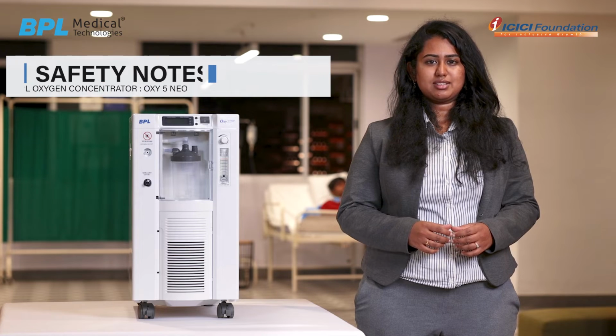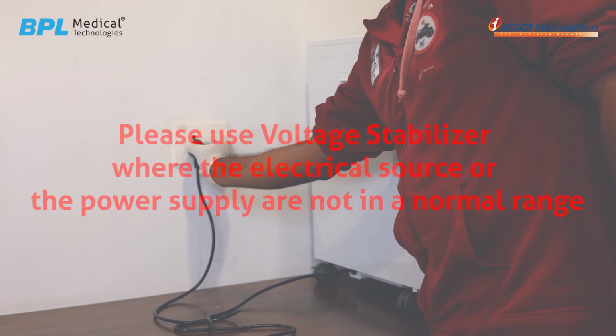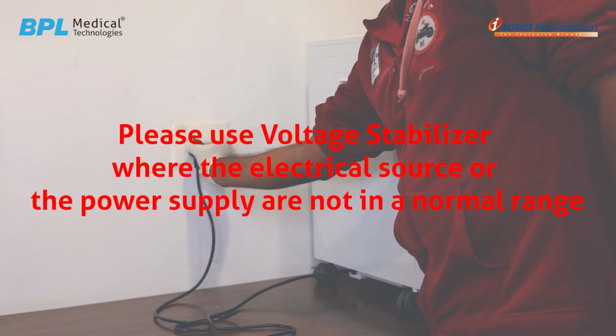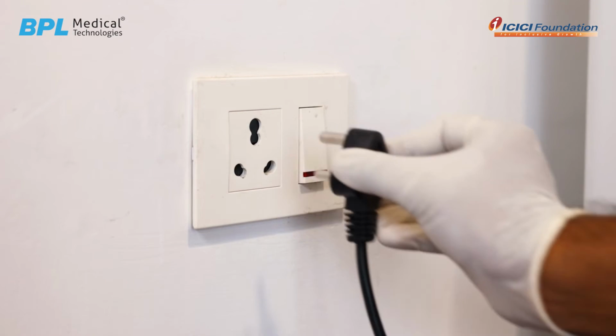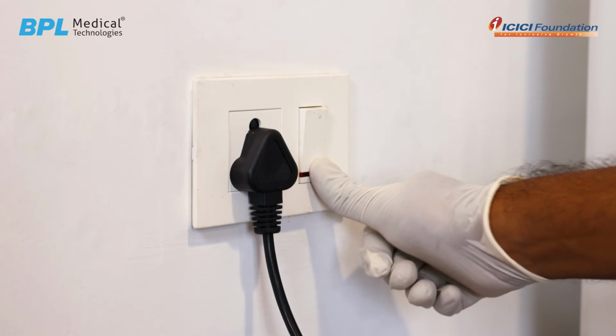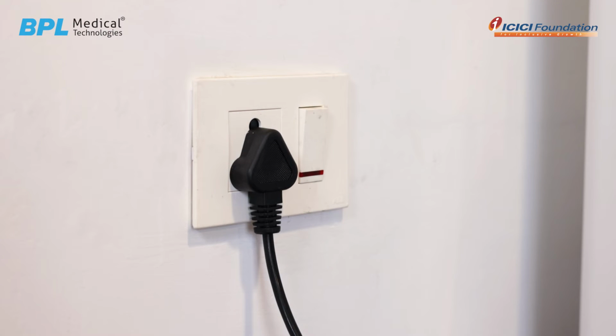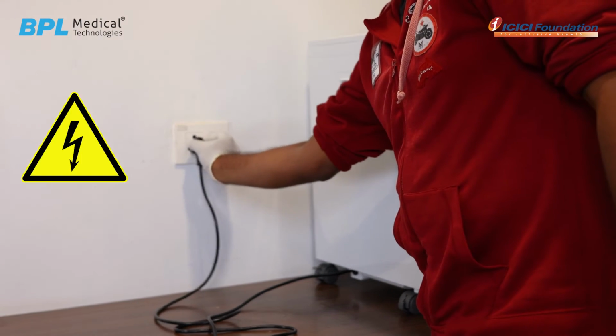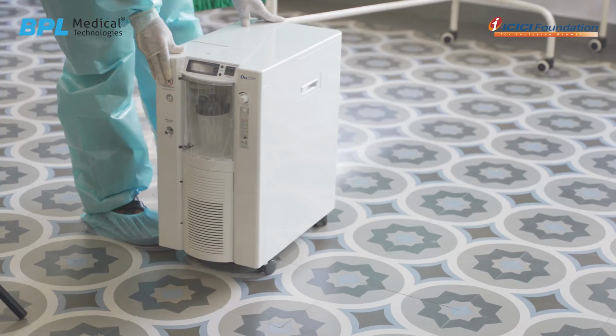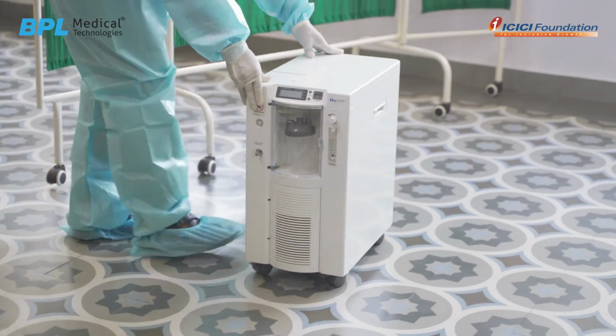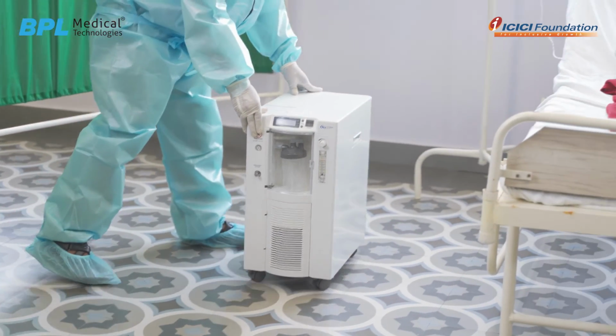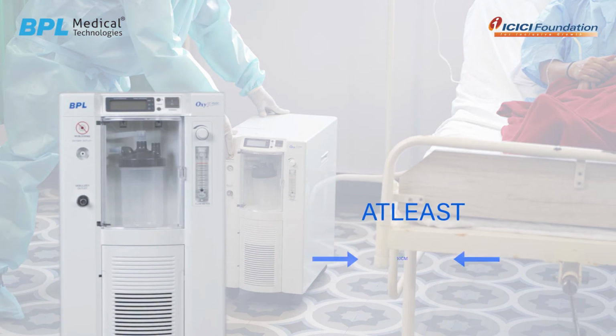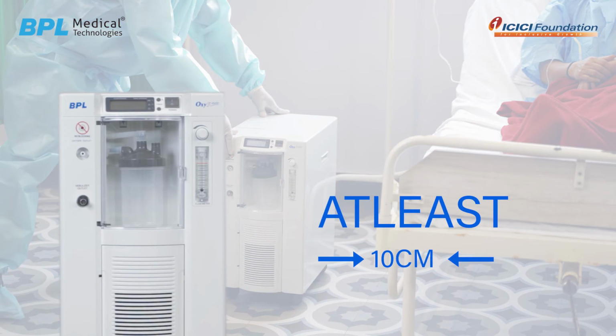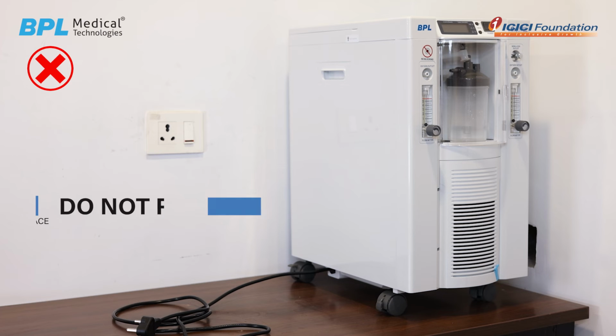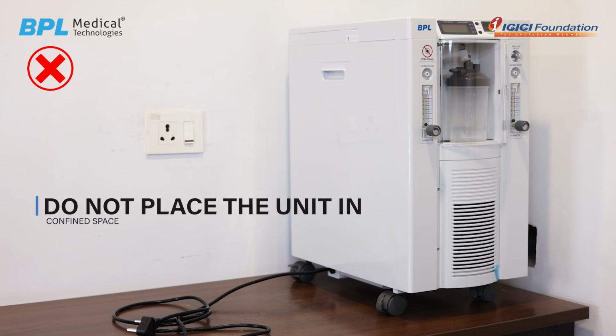Safety notes for maintenance. Please use a voltage stabilizer where the electrical source or the power supply are not in normal range. Connect the oxygen concentrator only to a grounded 3-wire receptacle. Do not plug the oxygen concentrator into any loose power socket. Place an oxygen concentrator in a room in such a way that all sides are at least 10 centimeters away from the wall, furniture or any other obstruction. Do not place the oxygen concentrator in a confined space.